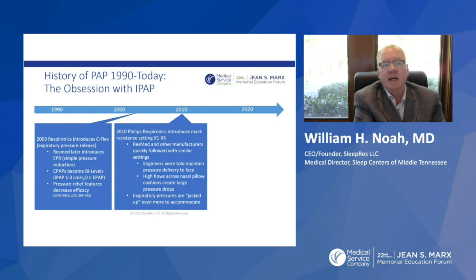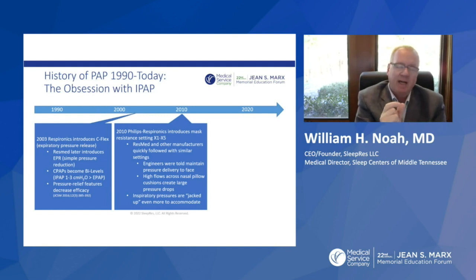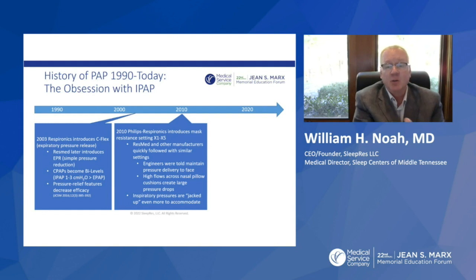So starting in 2010, Philips introduces the mask settings 1 through 5. You put it on the side of the cushion and you enter in the machine. And so when you put a small nasal cushion in, it has more resistance in it. Guess what? It's going to jack that IPAP up even more to overcome the pressure drop that's actually comfortable for the patient. So this is where it happened.